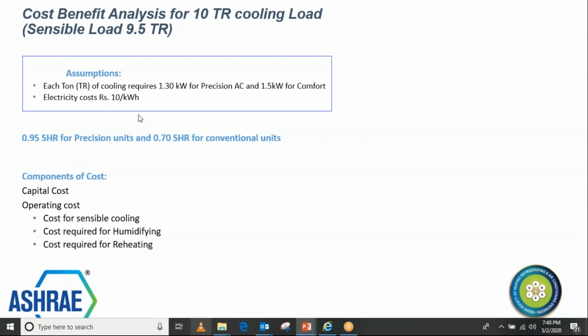On kilowatt per TR, it is 1.3 for precision and 1.5 for comfort. This may change a little in comfort or precision as well, because a lot of new technologies have come up on both sides. So this may come down slightly on both sides, but the difference will still remain because of the kind of components used in precision AC. This is the cost analysis and the operating cost analysis. The operating cost analysis is done for the sensible cooling required for 10TR, and the humidification and dehumidification cost for these two.